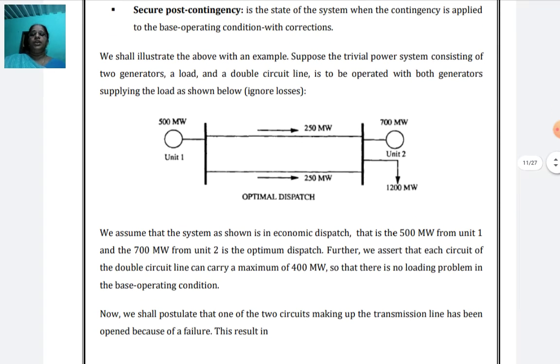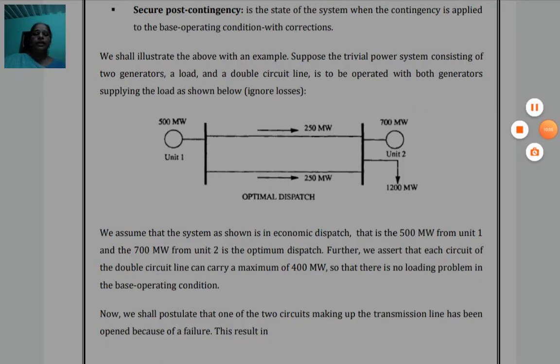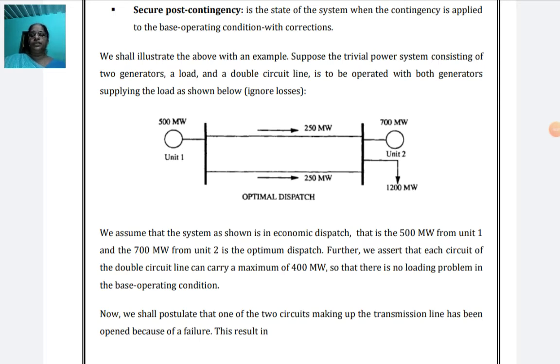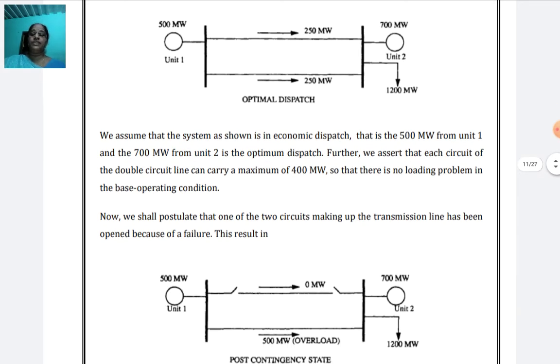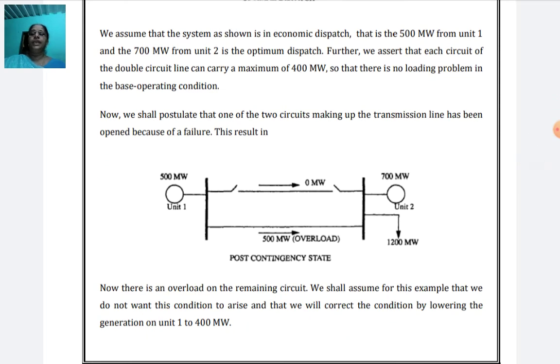First one is optimal dispatch. Here now you see the diagram. From the diagram, we are using two generator units, unit 1 and unit 2. Unit 1 generation capacity is 500 megawatts, unit 2 generation capacity is 700 megawatts. Then two lines we are using, transmission line 1 and 2. Both lines carry 250 megawatts only. Because unit 1 generated 500 megawatts, this 500 megawatts is carried by the two transmission lines. Our load demand is 1200 megawatts only. So in this case, no problem happened, no outage happened. Therefore this is nothing but optimal dispatch only, but this is not a secure system only. Any contingency can happen in this state.